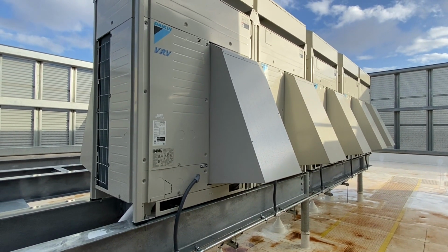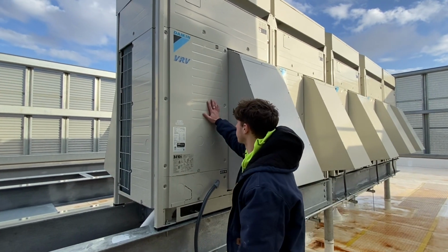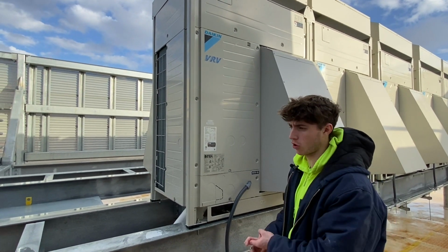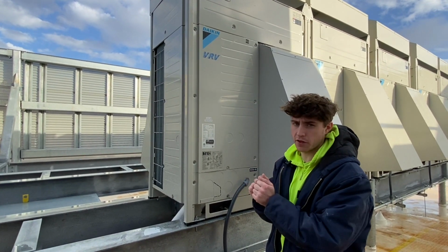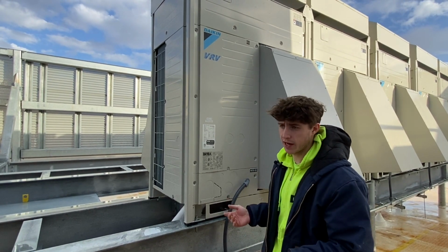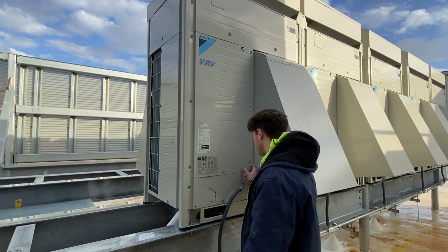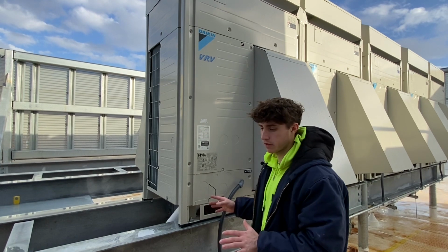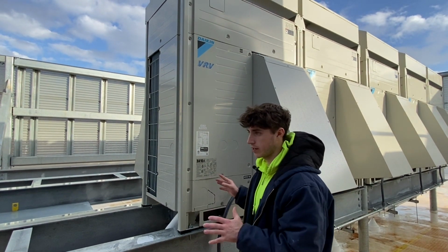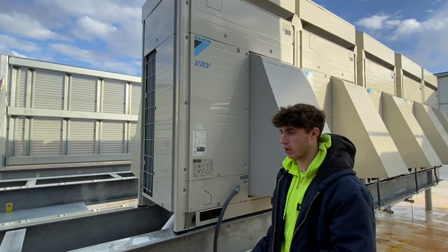After that, I think for the most part, you can always open up the inside of here. Just double check the inside, make sure there's nothing wearing down on the inside, like your pipes are not rubbing together with any other pipes. Basically, you want to make sure there's no wires that are disconnected and are loose or something like that. And you just want to make sure that all your insulation and all that kind of stuff is all good to go. So make sure that all that is tidied up, and make sure all the coils are washed, and you should be good to go for that maintenance for that time.